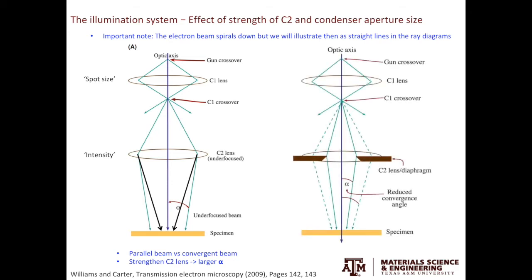We can also use the size of the condenser aperture to tune the convergence semi-angle. If we use a smaller C2 aperture, then we will have a smaller convergence angle. If you recall what we learned in the electron sources video, the value of alpha can directly affect the beam diameter, or the probe size, which determines the STEM resolution. Larger alpha leads to larger numerical aperture and improved resolution based on the diffraction limit.